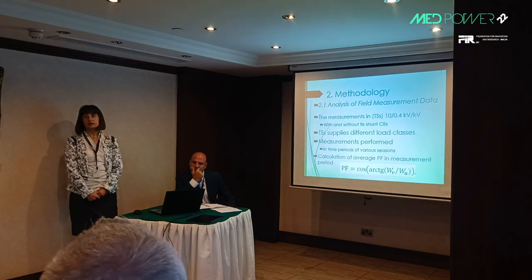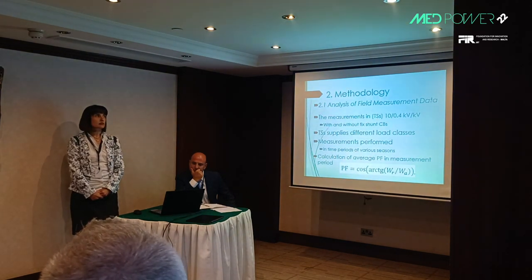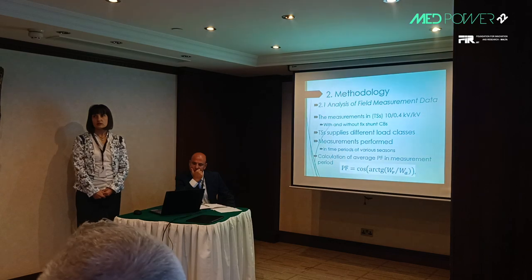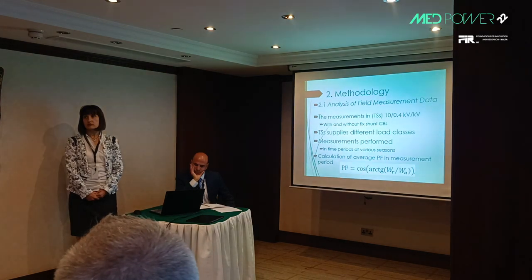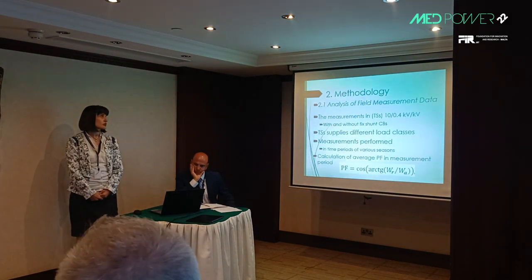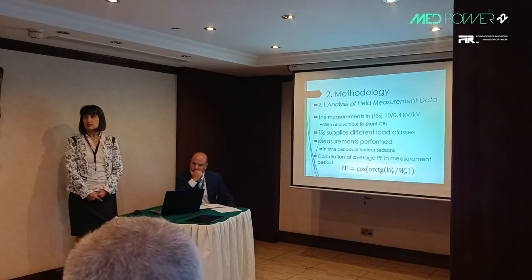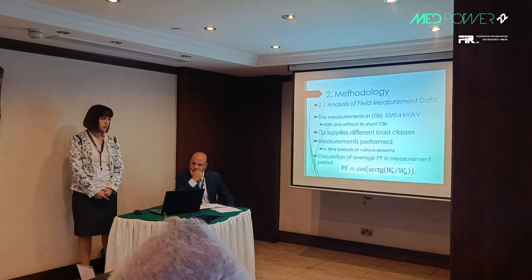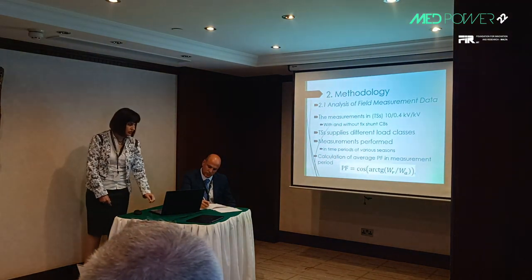A methodology for improving power factor in distribution networks is presented in this paper. It is based on measurements in distribution networks on the lower-voltage side of transformer substations, 10 to 0.4 kV, and in transformer substations that supply different load types. Measurements were performed in different seasons and in transformer substations with and without capacitor banks. At the end of measurements, average power factor is calculated.